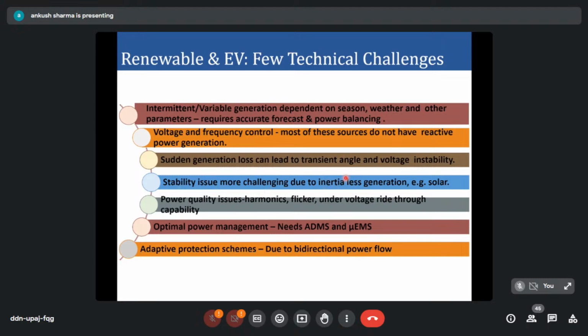Stability is more challenging because inertia-less generation will reduce the overall inertia of the system. As I mentioned, in a conventional power system, since thermal power plants have huge mass in terms of big generators, their inertia has the capability to absorb small faults, and the system doesn't get out of synchronism. But once we have more solar penetration, which does not have any inertia, there will be more challenge in terms of transients, in terms of faults, and how we will address the stability issue in the system.